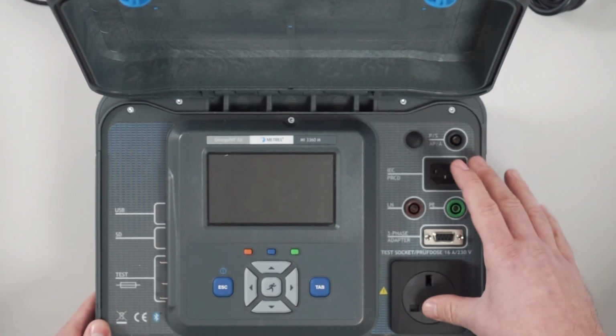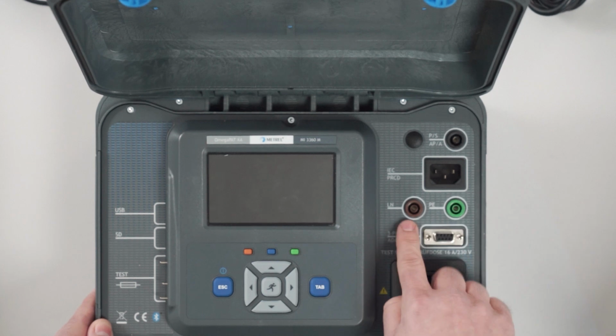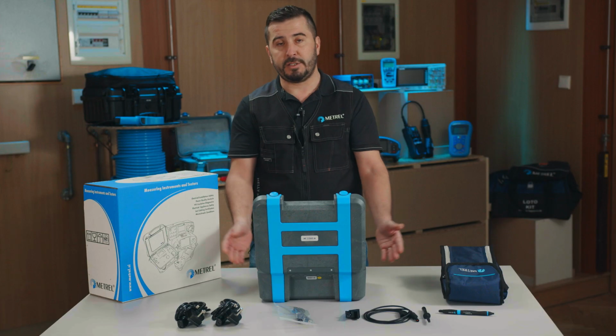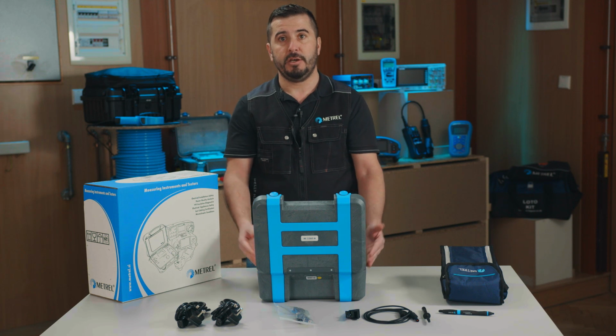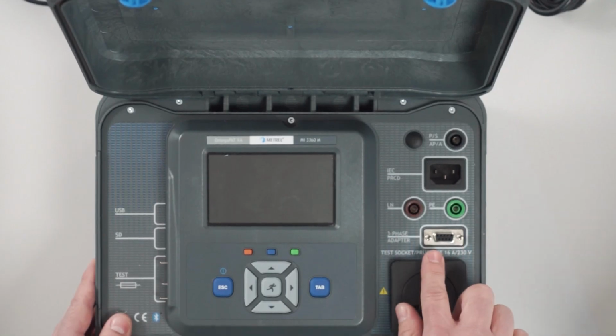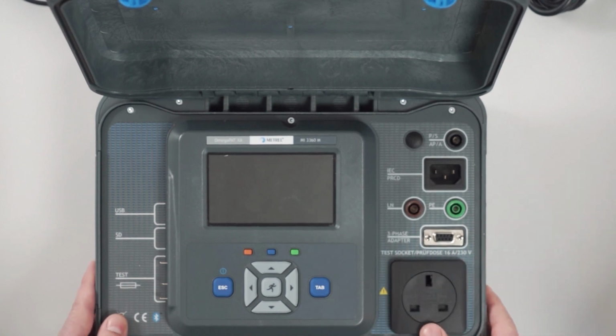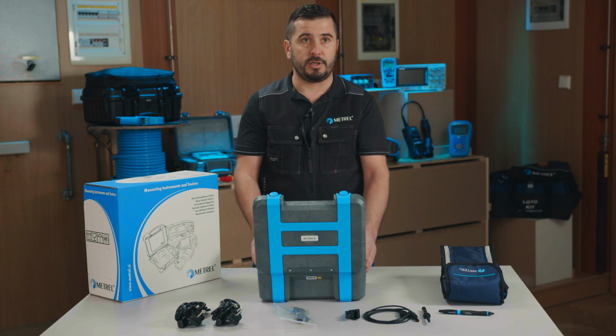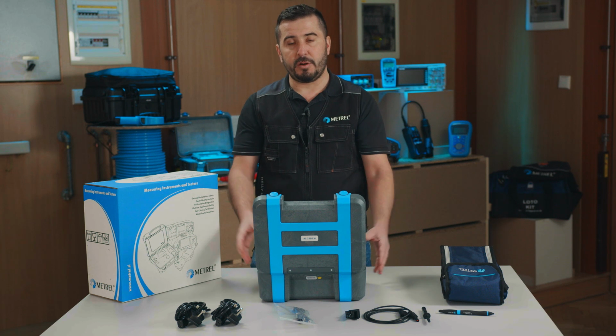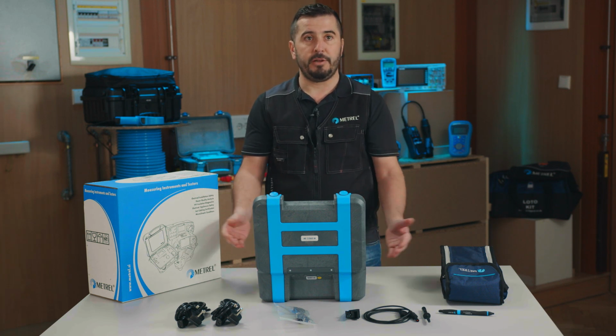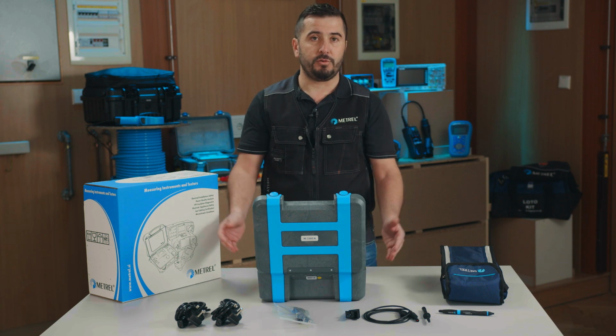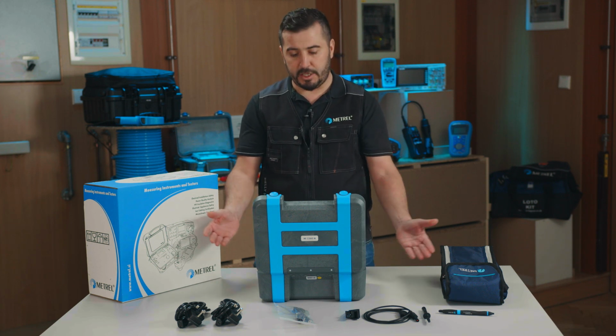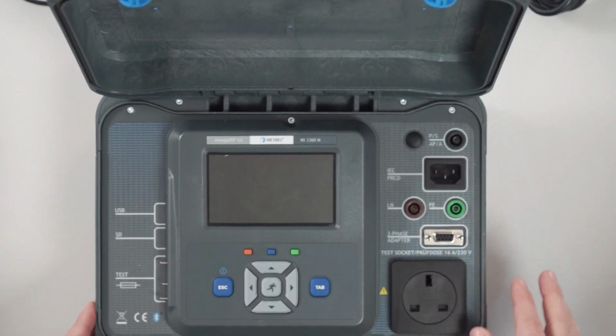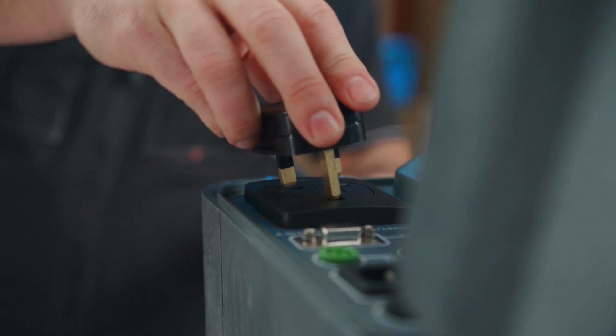Also, if these extension leads are equipped with an RCD, all these tests will be performed between these two measuring ports. Then we can see two additional ports, brown and green, for testing appliances which are fixed connected. Then we have an additional 9-pin communication port, where you can also connect the active 3-phase adapter, which can be used for testing bigger appliances and bigger electrical equipment, and we can measure real leakages and also different connections of three-phase cables. Of course, the last one here is our mains connector, and from this one we perform all the needed testing.